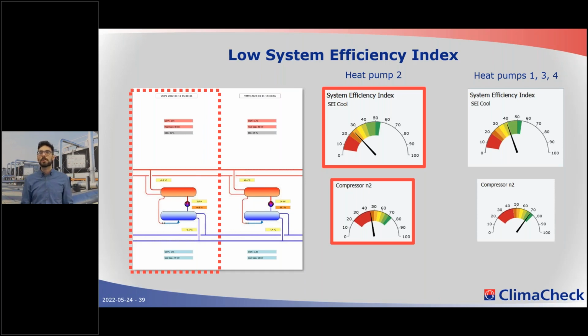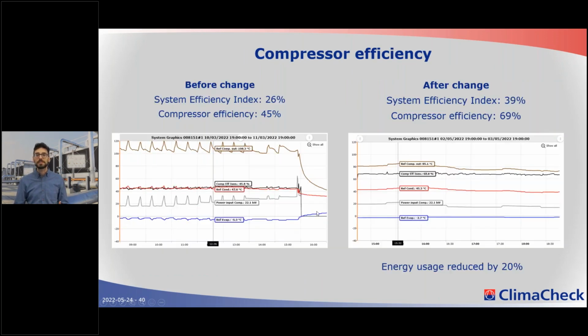So we contacted our partners responsible for the system and asked them to shut down and change the compressor. This is an extreme case where the compressor was performing terribly. Comparing before and after the change, we reduced energy usage by 25%. Our system efficiency index, showing total system energy, went from 26% to 39%. The compressor efficiency, showing how the compressor is working, was 45%—a terrible performance compared to after the new compressor, where we now have 69%. The result was a 25% reduction in energy.